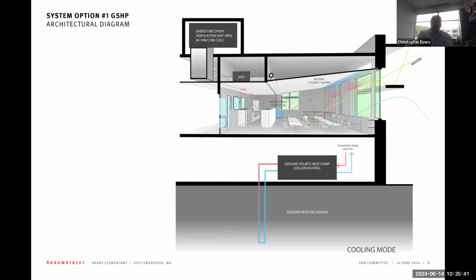Okay, so Mark and Roger, one thing to consider with this system: you're putting the infrastructure in. Say at the end of the day we had equipment failures, or all of a sudden we're going back to gas because the grid can't keep up and the energy companies start raising their electric rates and everything else. You're putting the infrastructure in that could support a traditional heating, cooling system if you ever had to convert it. Where with a VRF, you're gonna have a network of refrigeration piping running through the building. VRF's becoming common, but there's a lot of changes with refrigerant type. Gases are changing; refrigerants are going to a flammable gas. I don't know if you guys are facing any of those challenges with running refrigeration and fire rating and 2-hour ratings now.